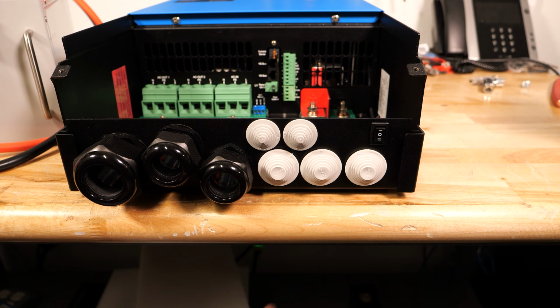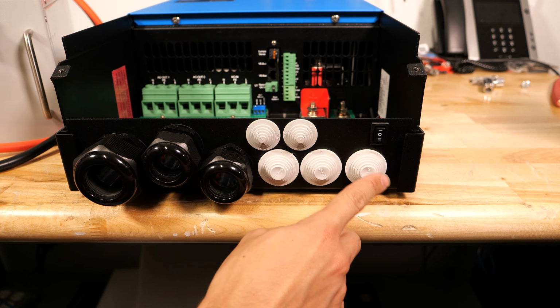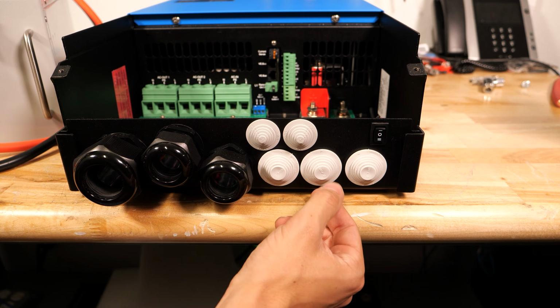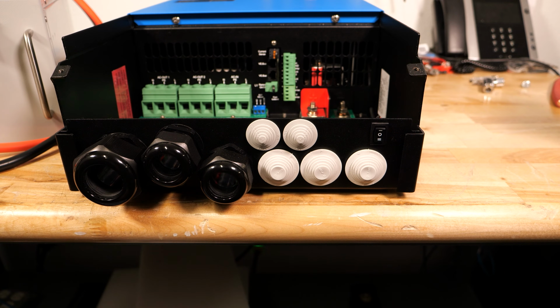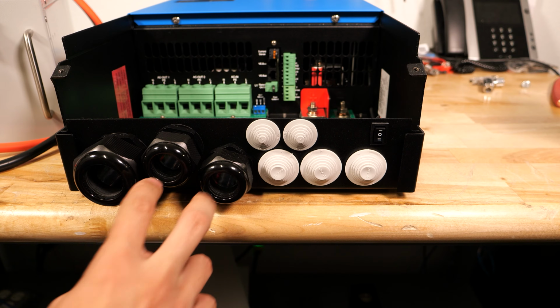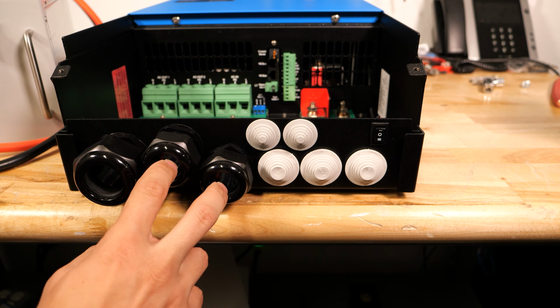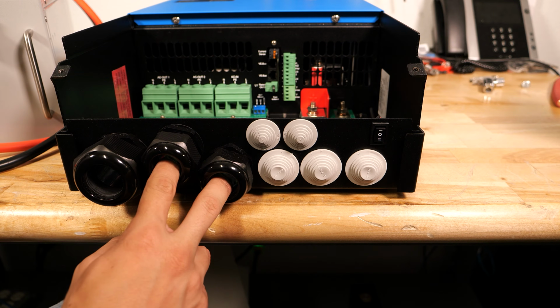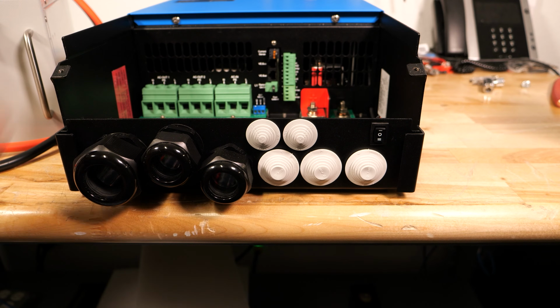Moving over to the bottom, we have a power switch here on the right. There's 3 entries here that you can cut off at various different steps depending on your cable size. There's a couple other smaller ones up here that you can use for your VE bus communication cables, or if you were using any of the auxiliary relays. And then they have 2 entries here and another one here. These look like they're roughly a 1-inch conduit opening knockout in here.